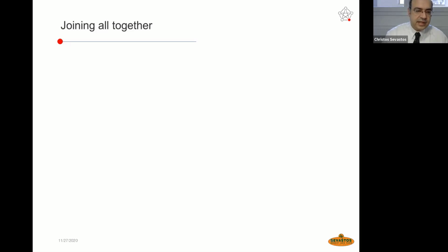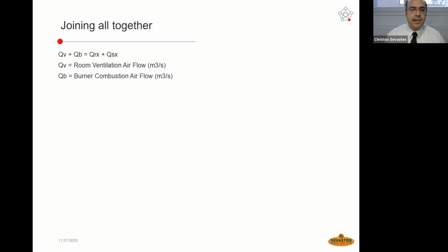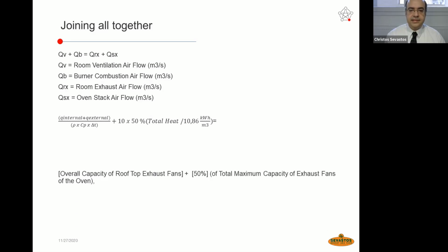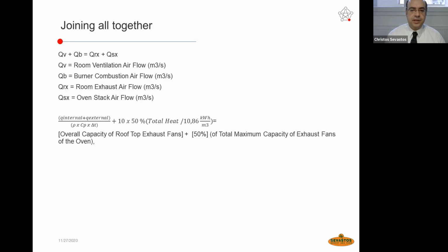After all these exhausting calculations, factors and variables, if we would like to join them all together, we are referring to the mass balance. Air ventilation rate, the room air ventilation airflow, plus the burner combustion airflow, those two are the air supply towards the oven and the room, covering the burning necessities of the oven, should be equal to the room exhaust airflow plus the oven stack airflow. This is the main mass balance equation applied in areas where we have air ventilation in a tunnel oven.